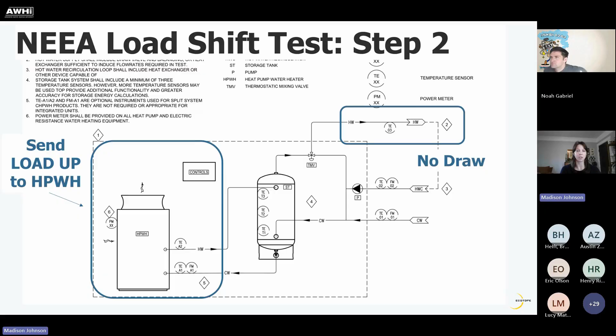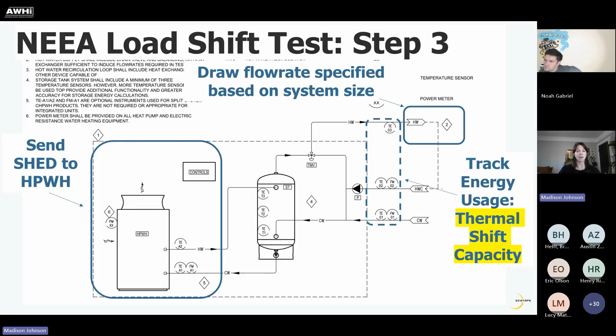And then the exciting part is step 3. Once we're fully charged, we send a shed signal to the heat pump water heater and start a draw period, where this draw flow rate is specified based on system size. And then during that drawdown, we track all the energy that's exiting the system until the heat pump water heater is triggered on in that shed state. So this is giving us our thermal shift capacity. It's the same metric that Ecosizer is outputting. We're just measuring it in the field this time.